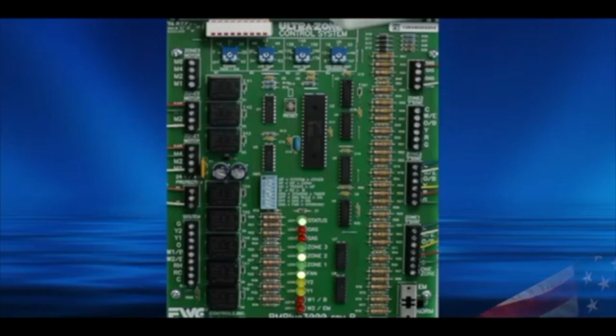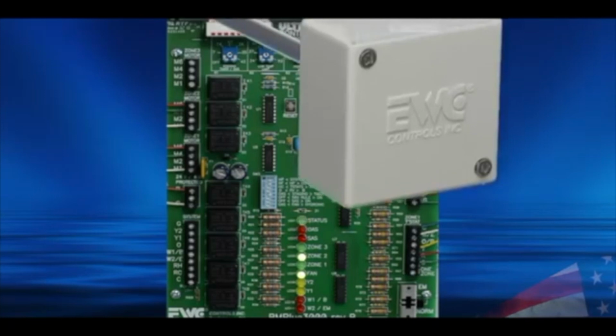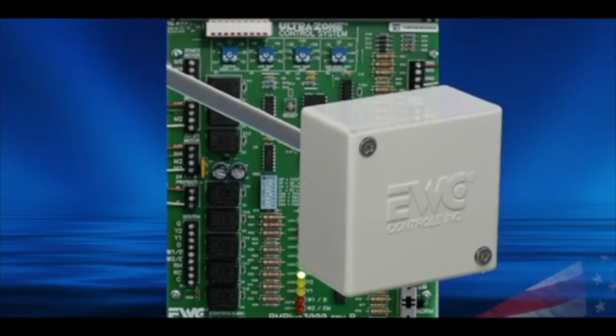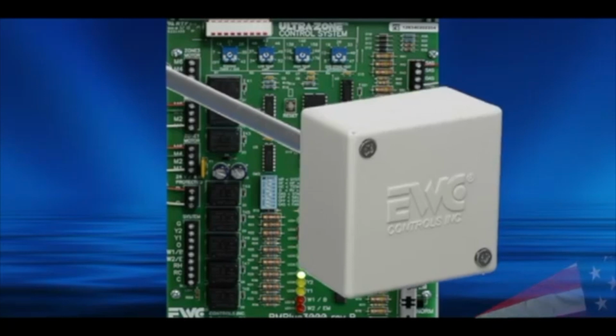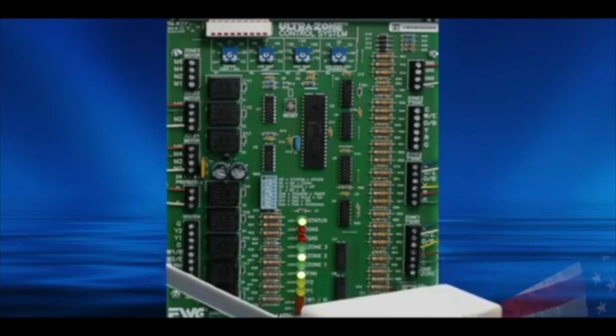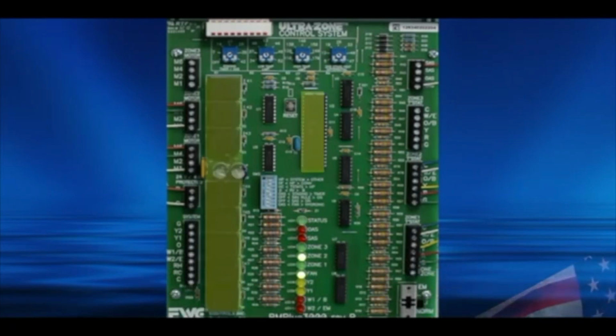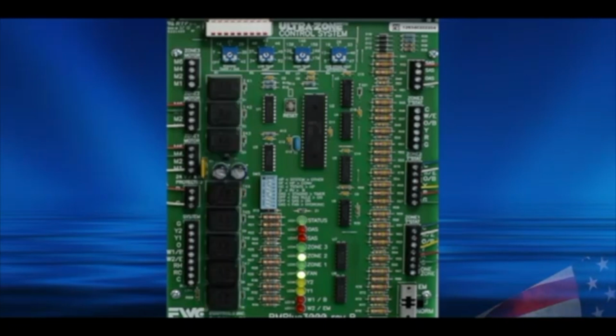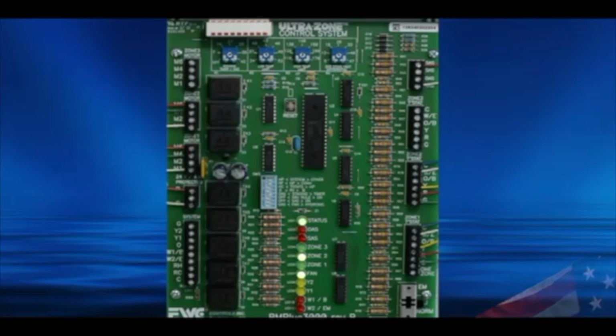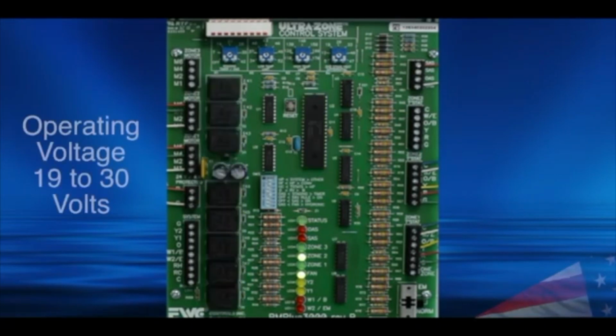A supply air sensor, SAS, which has cooling limits and 2-stage heating limits, is included with every panel. This is not an option. It protects the equipment from overcooling and overheating the system. The BMPlus has a 24-volt conditioning circuit which protects the board from EMI and makes the board extremely stable. The processor includes a watchdog circuit which maintains proper operation and constantly monitors voltage.